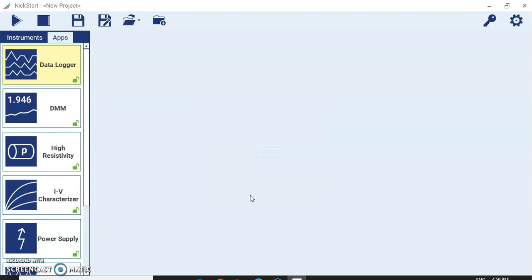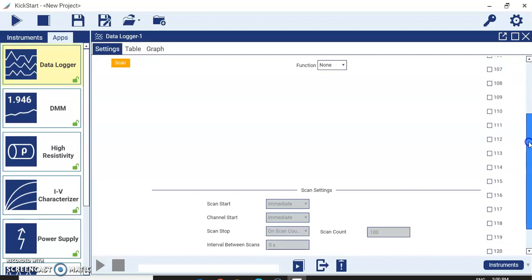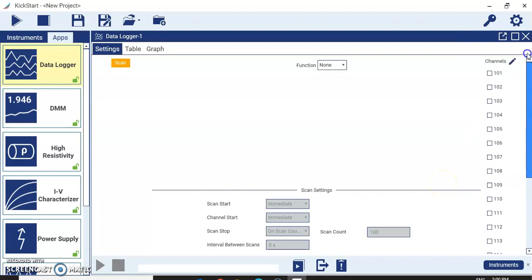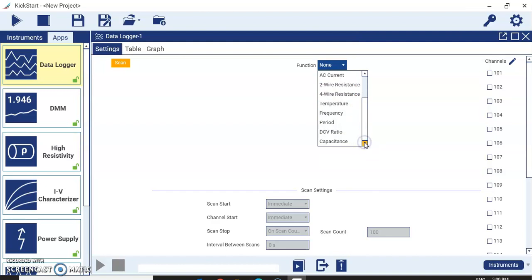KickStart will now launch its configuration menu. You can see the Settings, Table, and Graph tabs. In Settings, you have all channels — since I selected the 7700 (20-channel card), channels 1 through 20 are available, with channels 21 and 22 dedicated to current measurements. For each channel you can select measurement functions such as DC voltage, AC voltage, DC current, AC current, two-wire resistance, four-wire resistance, temperature, frequency, period, ratio, capacitance, and so on.